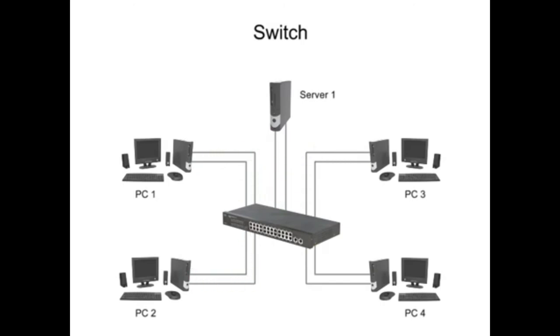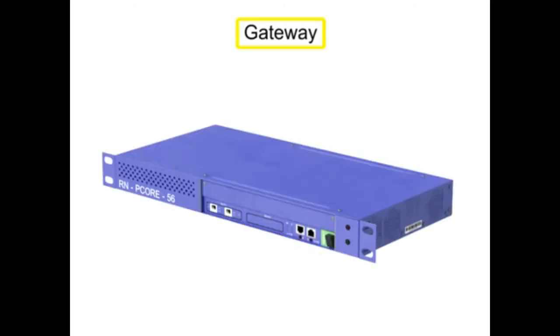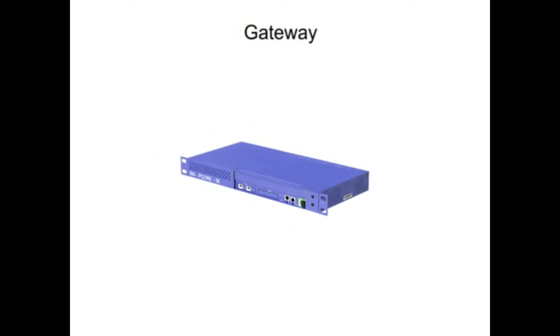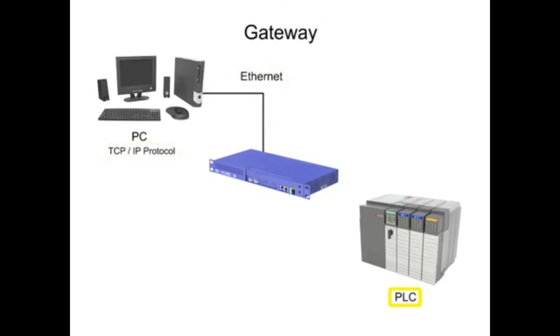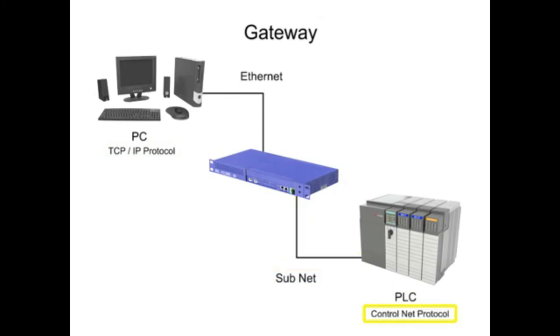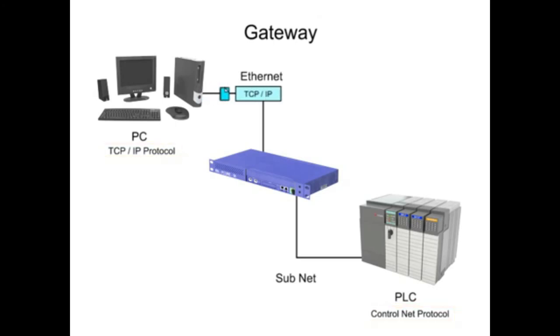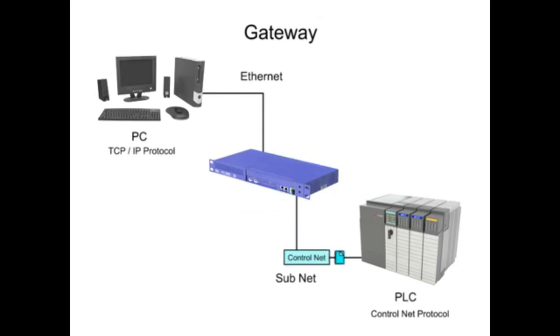When two segments of the same network have different communication formats, a gateway is needed to connect them. A gateway performs a conversion function so that a computer on an Ethernet network using a TCP IP protocol may communicate with a PLC on a subnet using the Control Net protocol. Even though these two protocols are incompatible, the gateway can connect them on the same network and allow them to function together.